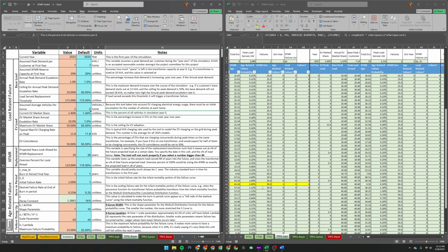If you think that the step from 50 to 80 is insane, that's way too much, just make your demand escalation less here. And if you do that, you're going to see it went from 80 to 71.1. Obviously, nobody makes a 71.1 kVA transformer. That's another part of it. You want to step into the interval that makes the most sense.